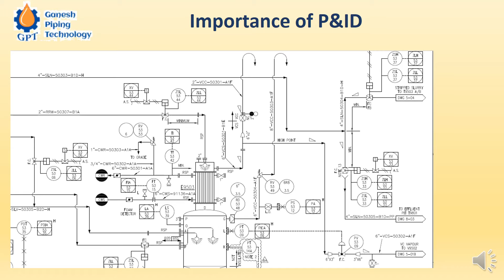Of course, we are going to see this in the coming slides, and there is a limitation when you take the MTO from the P&ID. The limitation is you cannot get the pipe length and number of elbows. Every other item is covered, like T, reducer, valves, flanges, gaskets, bolts, whichever are required for that given project. Everything can be estimated except pipe length and elbows. This information we can get from the elementary layouts which are developed in the preliminary stage.